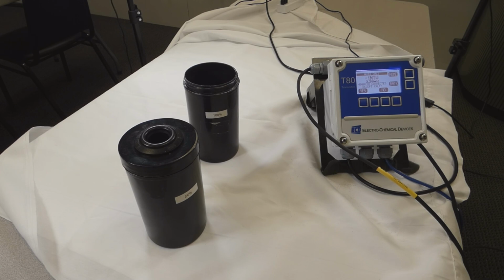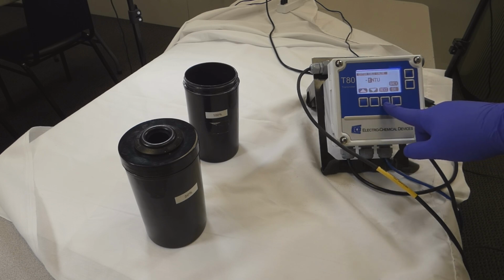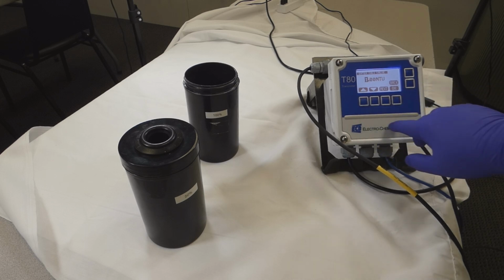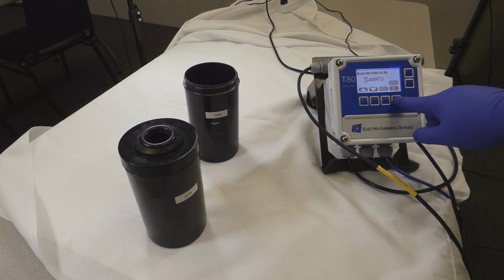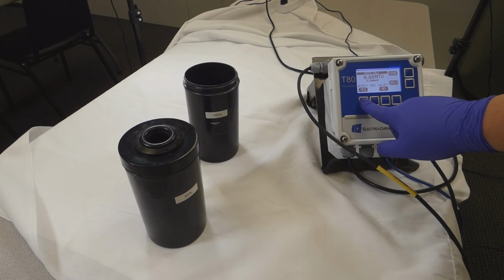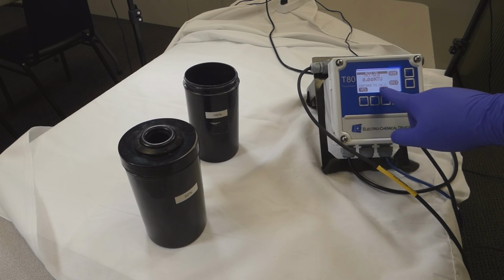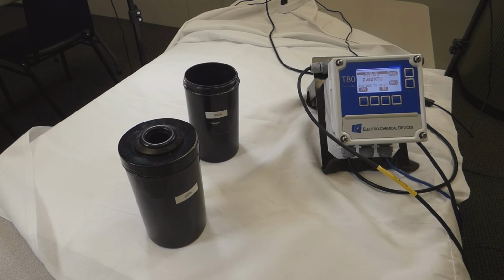Alright, now after the stabilization, the transmitter will ask you if you need to correct the value or not. In this case, we will need to correct it. So we say no and enter in 0. Accept this value. It will ask us, do we want to move on to Cal 2? You will not at this point.